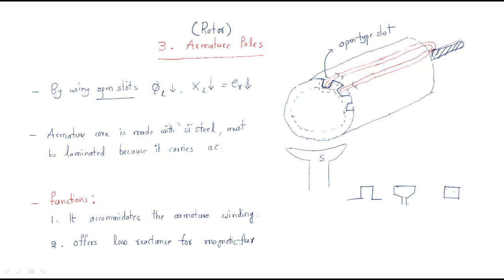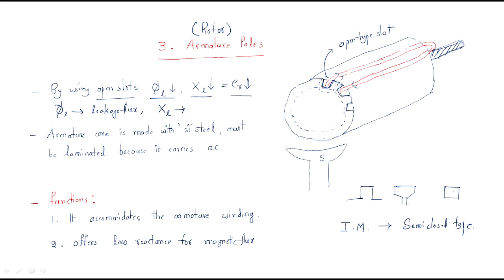Open slots are used in DC machines. In the case of induction machines, semi-closed type slots are preferred. In DC machines, open type slots are used because the leakage flux will be low and the leakage reactance will be low. The reactance voltage (ER) will also be less. Here, φL is the leakage flux, XL is the leakage reactance, and ER is the reactance voltage.